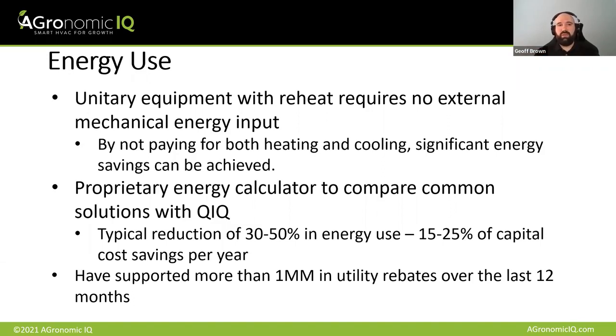One of the tools that we've built is an energy calculator that allows us to compare some common solutions with the AGronomic IQ solution and what that looks like. In general, the unitary systems with integrated reheat have something like a 30 to 50% savings in annual energy use. That represents 15 to 25% of the capital cost of that equipment on a per year basis. So when you're looking at the overall return on investment of your facility, that energy use reduction is important. Obviously it makes a bigger difference in a place like Puerto Rico, where you're paying 25 to 30 cents a kilowatt hour, versus Oklahoma at 7 or 8.